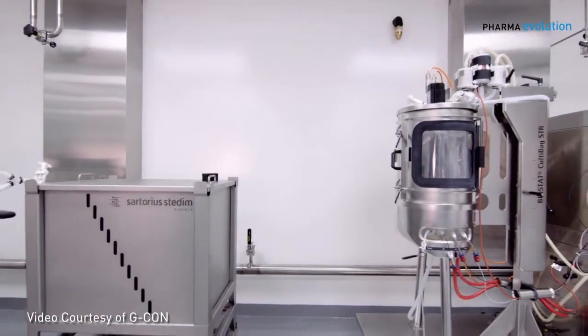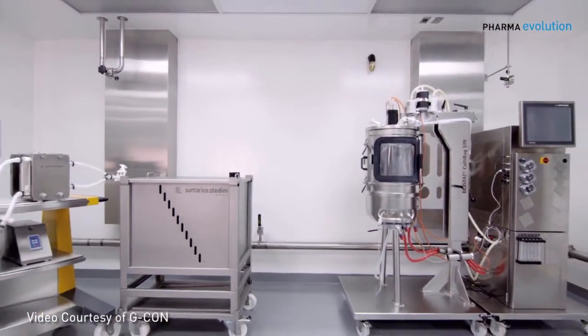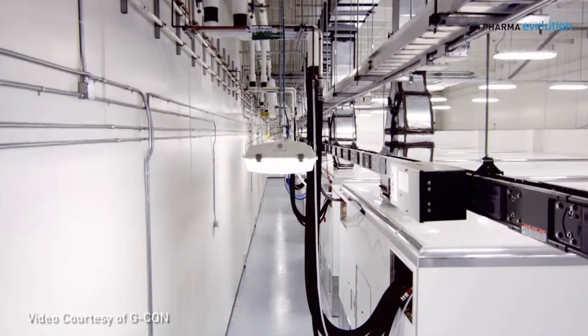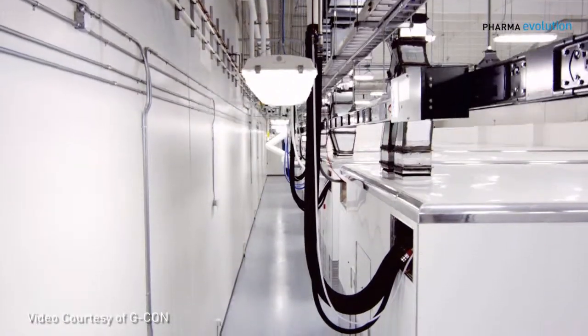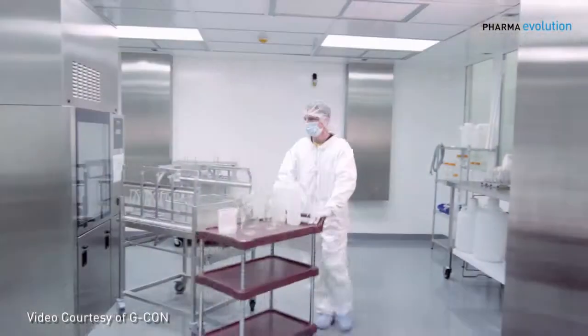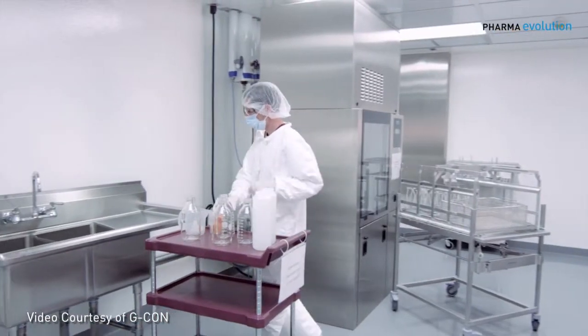These mobile pods are on air bearings — they float into the facility and you can have a downstream process stacked with pods one after the other. They are easy to decontaminate with vaporized hydrogen peroxide, and you can use them for multi-products, not just one.